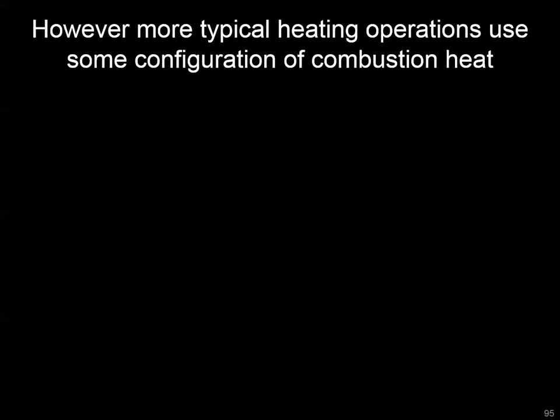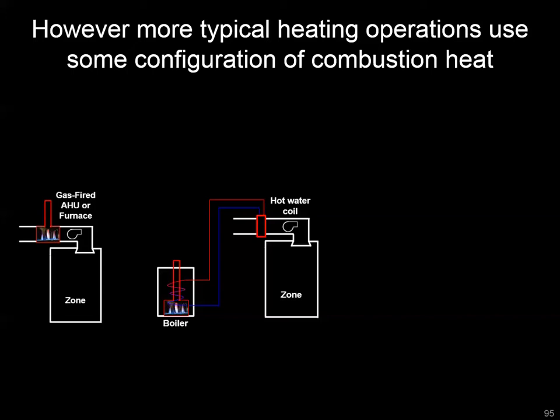A lot of typical heating configurations in commercial HVAC are going to leverage some combustion process, and there are a couple of flavors of that. The next simplest would be a furnace or a simple air handler that has a gas-fired oil or natural gas air-to-air heat exchanger. In larger systems, we may see a hot water boiler that uses an intermediate hydronic water loop to take water from an air-to-liquid heat exchanger at the boiler to some coil or heat exchanger near the zone.